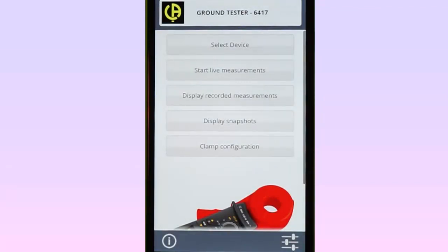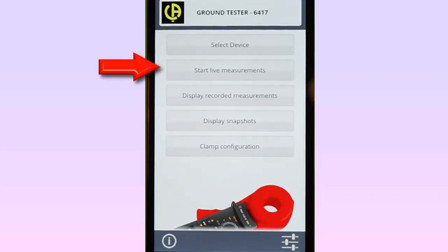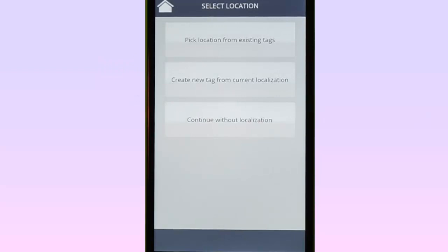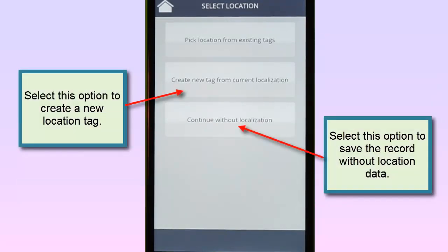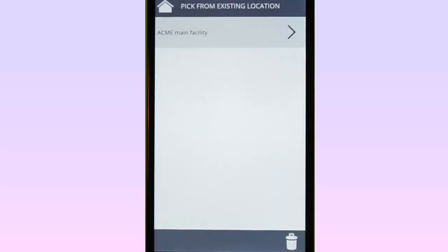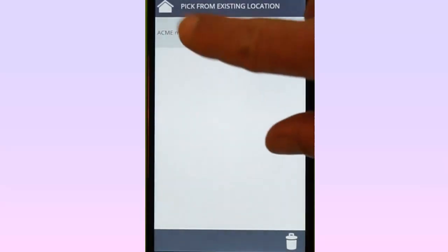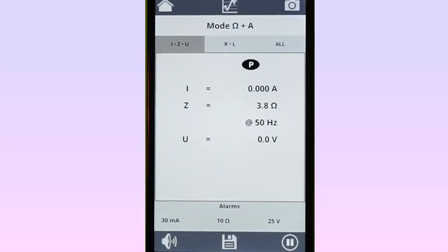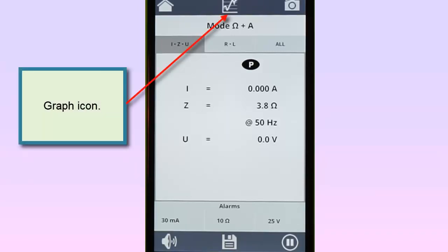With the instrument connected, you can now view data in real-time. To do this, select Start Live Measurements in the main menu. The Select Location screen appears, enabling you to create location information that identifies the measurement site. Select Pick Location from existing tags and choose a previously created location tag. The data currently being measured by the Model 6417 now appears on the screen. Real-time measurements can be displayed as both numerical data and as graphical trends.